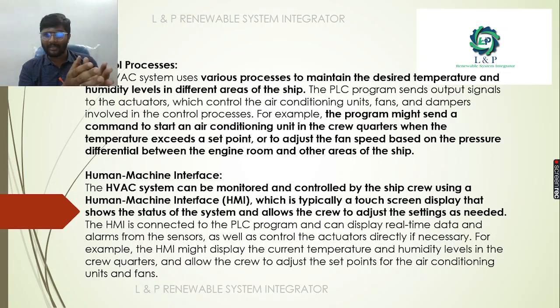We might write a program to send a command to start the air conditioning unit in the crew quarters, and when the temperature exceeds a set point, we need to adjust the fan speed based on the differential pressure between the engine room and the other areas of the ship. So we are using the human machine interface HMI system for monitoring and controlling. It will be useful for the ship crews. All the status will be displayed on this, so that whenever any adjustments are required, they can make them using these HMI screens.